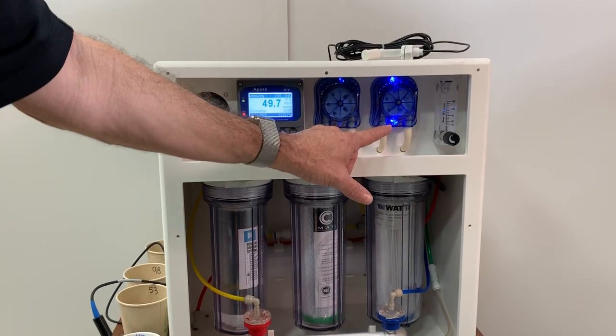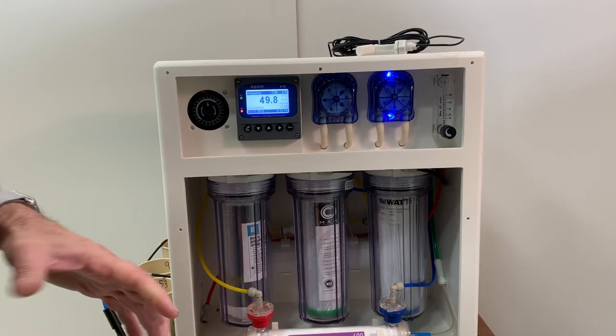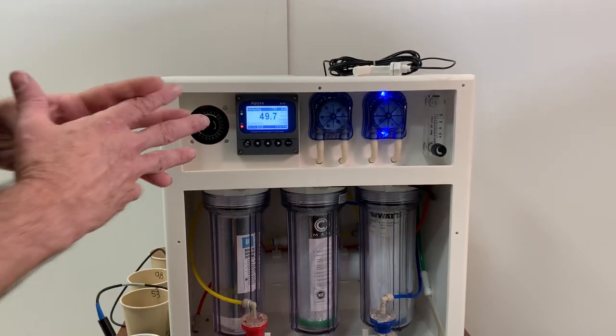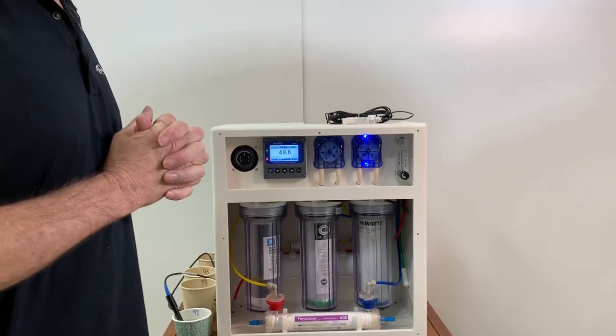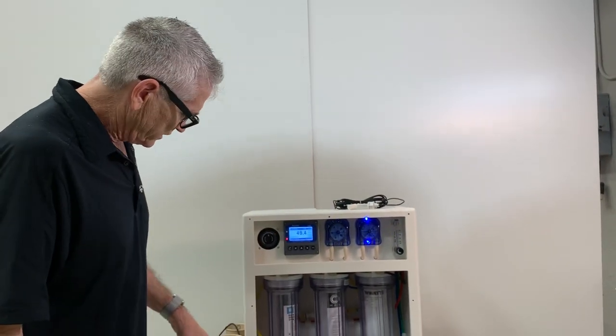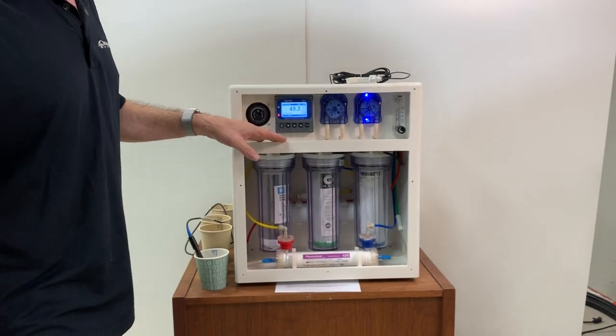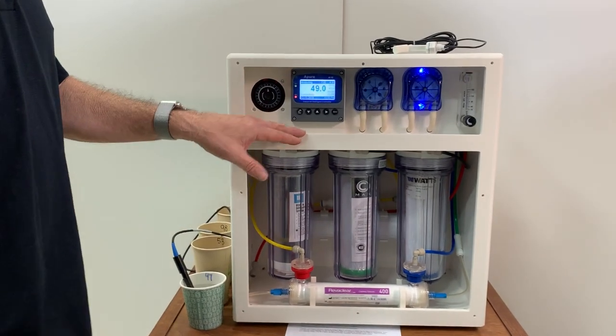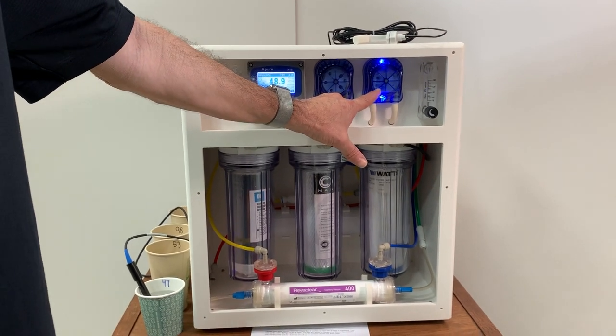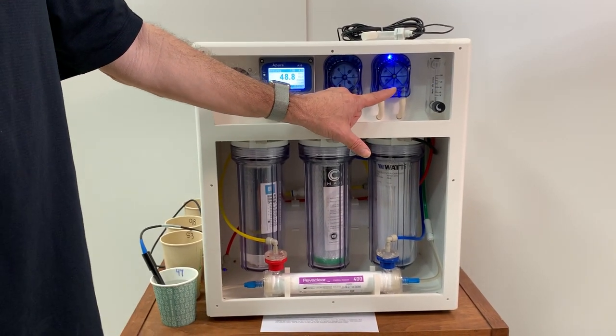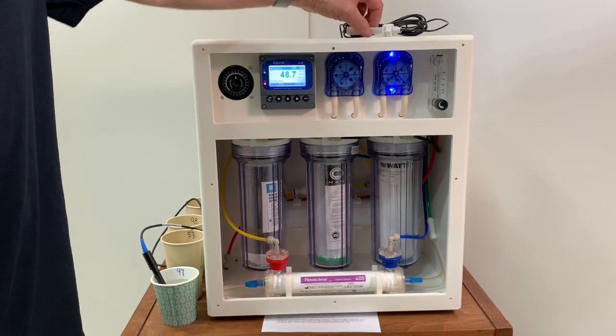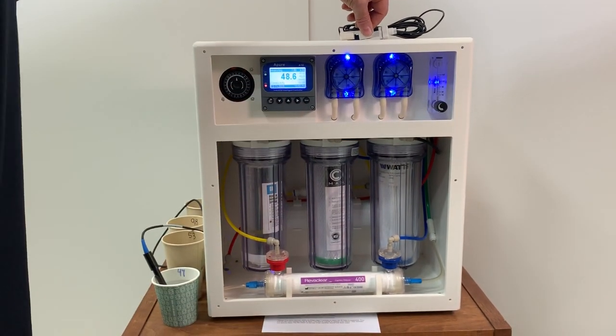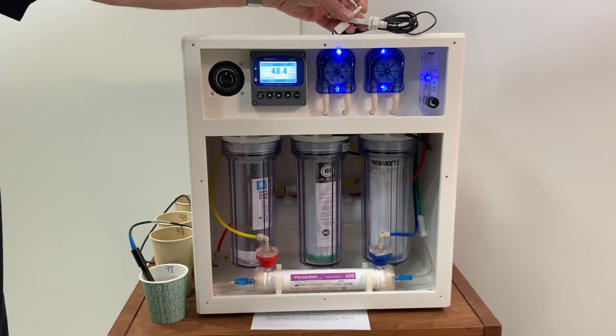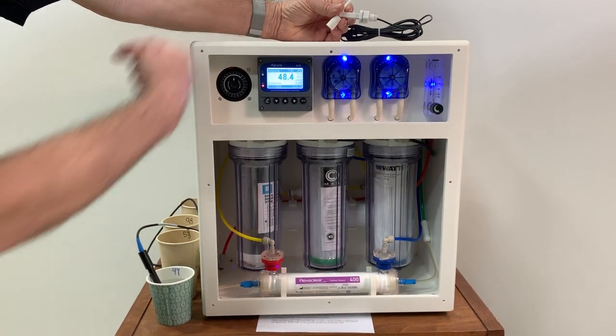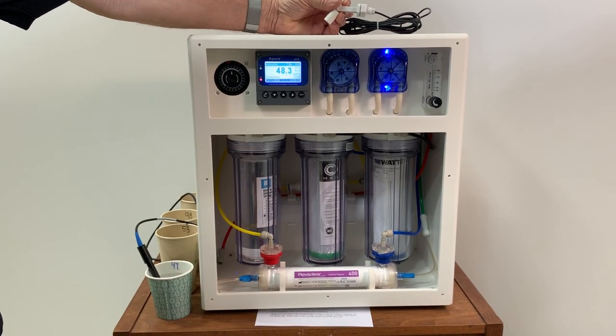Now it's back up. When I had taken the probe out, it went completely out of the water, and it told the machine that, hey, there's not enough salt in the system. We must shut down. But now that we're at 47, which is below our low setting, which I'm going to show you how to set, it's saying add salt to the tank. Now we can be adding salt to the tank the same time we're changing water. We can be adding salt to the tank the same time that we're just adding DI. If this float switch drops, it's going to shut this pump off.